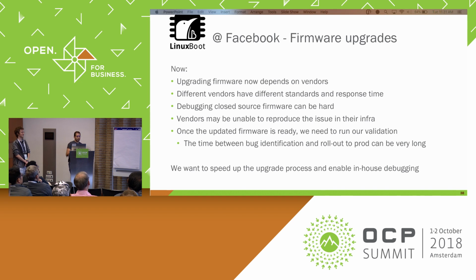Putting all these things together, let's assume that at this point the vendor has fixed the firmware. They hand off to us a new binary blob, and we need to run our own validation. So they have to do their testing. Let's go back. We have to detect the bug first, contact the vendor, get them to test it, validate the bug, fix the bug, and give us back the fixed images. Then we have to run our own validation, which is a second additional step that further slows down everything, and communicating with external companies is, of course, slower than doing everything internally.